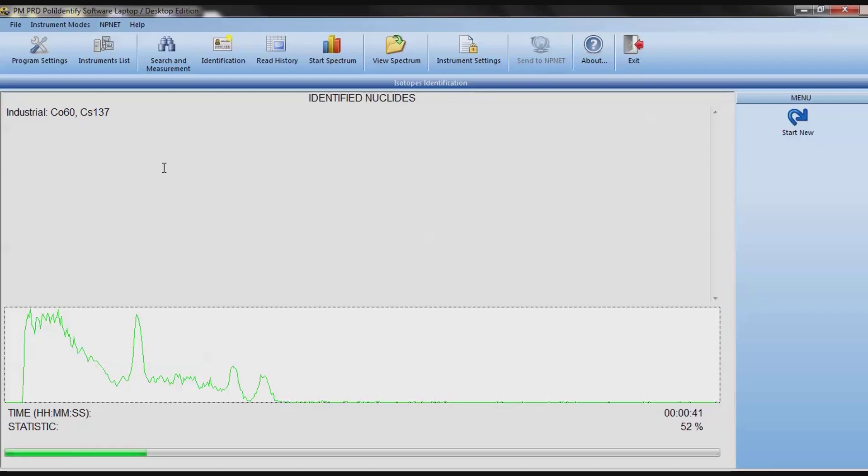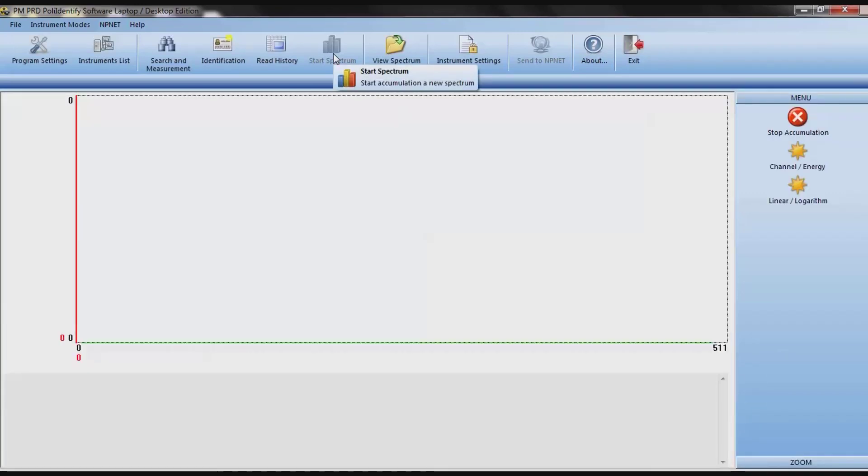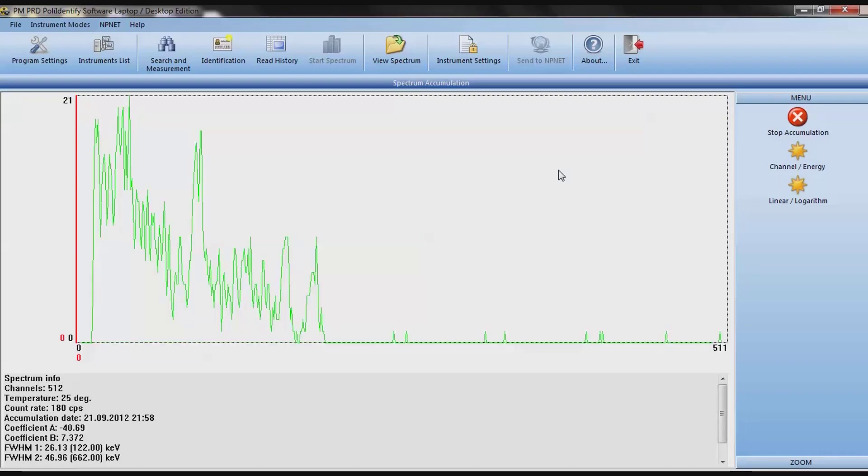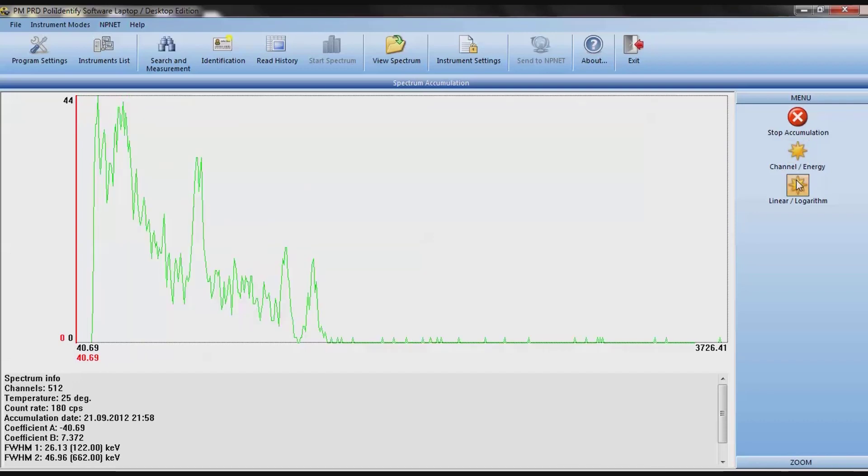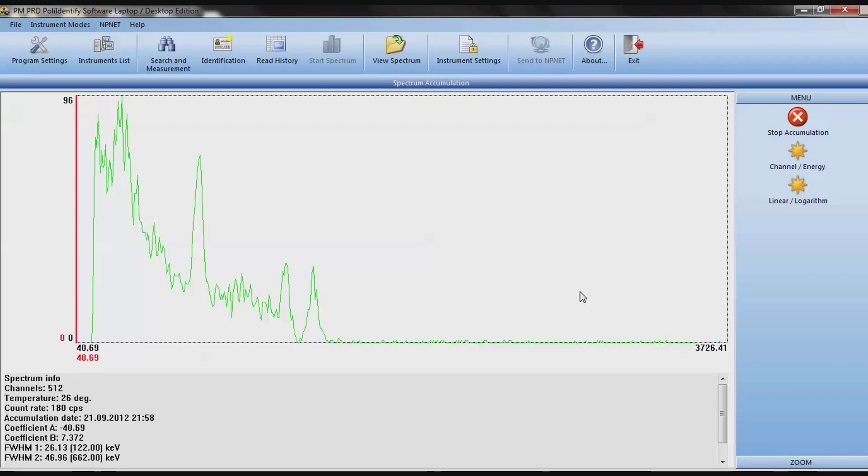If anybody's familiar with those spectrums or those isotopes, you immediately see the reason why it detected those. Now let's take a full gamma spectrum. And we'll see how this thing does. Now it takes a second to do a full gamma spectrum. We're almost done. There it is. You notice that looks like what you saw before, just a little bigger. We can change the channels into energy so we actually see the real energy. In the center of the screen, the peak dead down the middle is actually 662 kiloelectron volts. It's coming from cesium-137. The two that are on the right are coming from cobalt-60 at 1173.24 kiloelectron volts and 1332.5 kiloelectron volts.